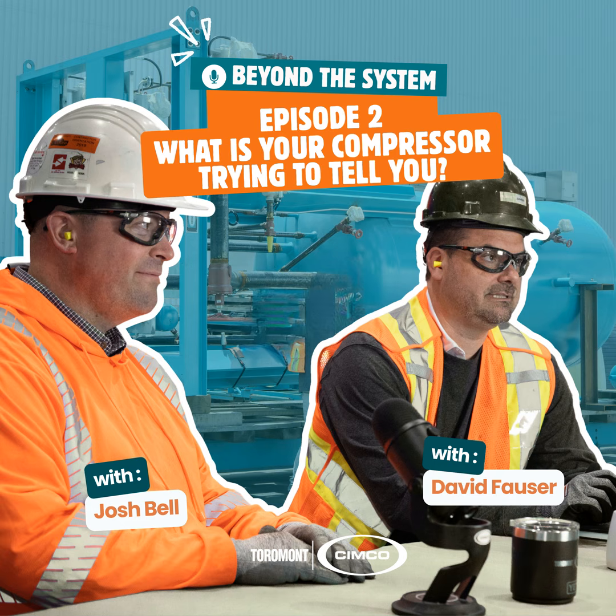And then, further than just what you're recording, I always liked operators or engineers or whomever is the guardian of the equipment to document the run hours as well, because I like to set service intervals off of run hours. I always carried a seasonal service interval, and then I always carried a run hour service interval. So if you didn't hit the run hours, but you were down for 4 months in the summer, well, cheap insurance, let's change the oil. So from an inspection perspective, your pressures, your temperatures, your run hours are all very critical.